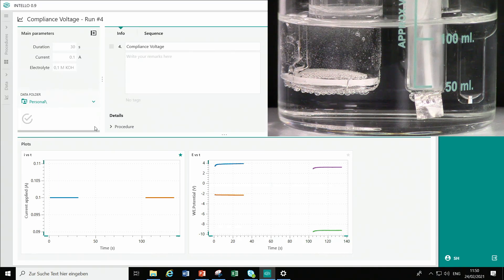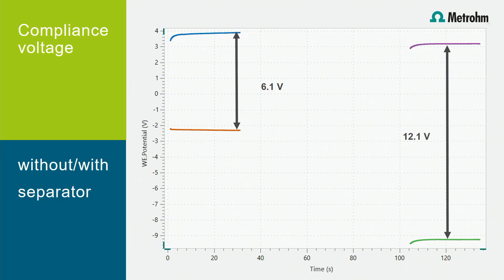To keep the current of plus 100 mA constant at the working electrode, a much higher compliance voltage is needed due to the potential drop at the separator. On the left side the measurement without separator is displayed and on the right side the measurement with separator. The voltage difference between working and counter electrode is the compliance voltage, controlled by the potentiostat to keep 100 mA constant at the working electrode. The compliance voltage had to be increased from 6V to 12V due to the glass frit. In our experiment we used a good conducting electrolyte and the frit had high porosity — if we used a less porous frit, the compliance voltage could easily reach values higher than 15V.